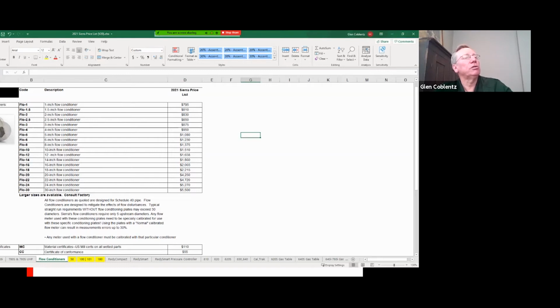Now, the reason why you might want to consider these very large flow conditioning plates is every once in a while, you will get into a battle with a multi-point system from FCI, from Kerrs, or other folks where they're saying, hey, guess what? We'll do a multi-point system for your 6-foot duct here, and you'll be in good shape. Those are incredibly expensive. And if you think about how a multi-point works, it's a pipe and one probe that goes across the pipe. Maybe there's 2 probes that go across the pipe. Now you're doubling the cost. But what happens with the flow here and here? It's not being measured, okay? So they're missing a lot of spots, and especially if they don't have the straight run of pipe, a multi-point is basically useless in terms of making an accurate measurement.